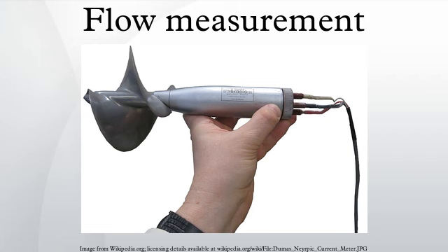Mechanical flow meters. A bucket and a stopwatch is an analogy for the operation of a positive displacement meter. The stopwatch is started when the flow starts, and stopped when the bucket reaches its limit. The volume divided by the time gives the flow rate. For continuous measurements, we need a system of continually filling and emptying buckets to divide the flow without letting it out of the pipe. These continuously forming and collapsing volumetric displacements may take the form of pistons reciprocating in cylinders, gear teeth mating against the internal wall of a meter, or a progressive cavity created by rotating oval gears or a helical screw.